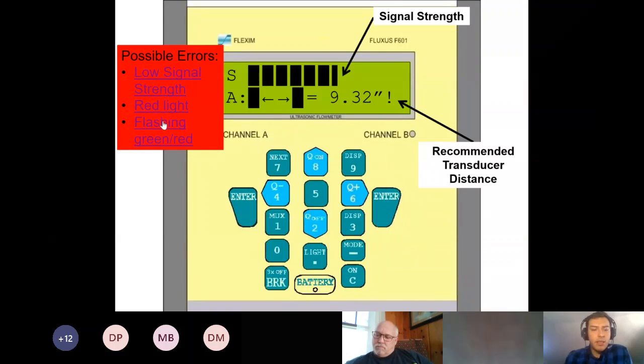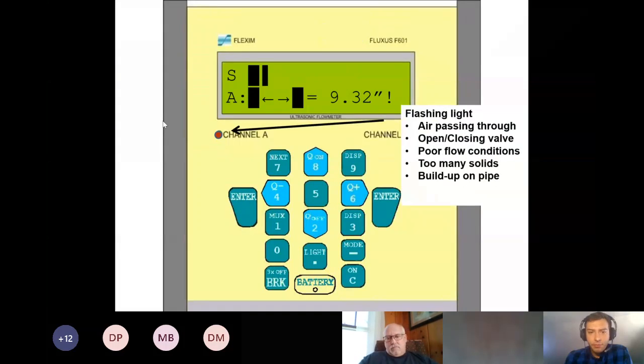The final error that you can get is a flashing green and red. You'll see that here. This could be a number of things. It could be air passing through the pipe. It could be turbulence from an opening and closing valve if the meter is very close to a valve. This could just be poor flow conditions. If you're coming off of a 90 and it's struggling to pick up good flow off of that, try to find somewhere with a little bit more straight run.